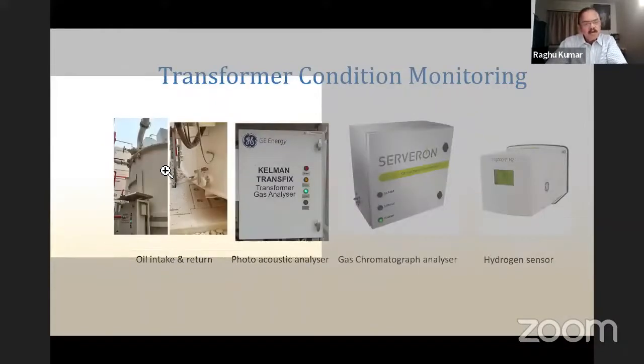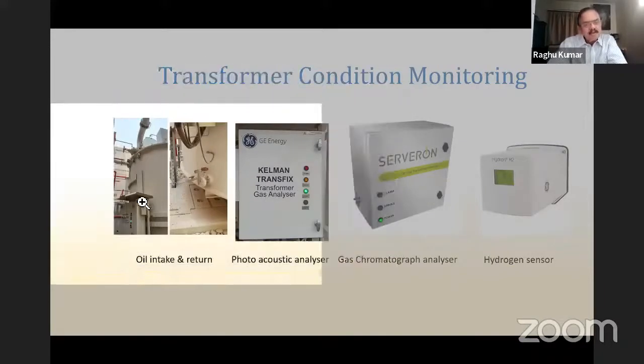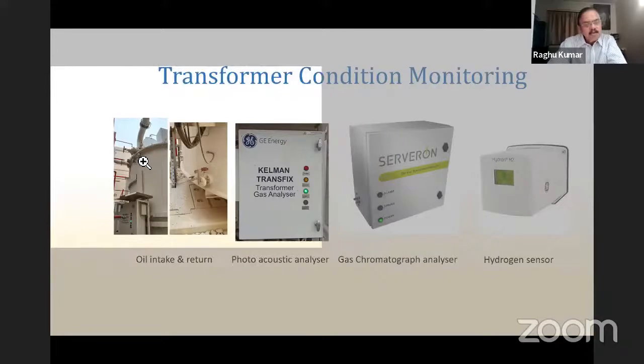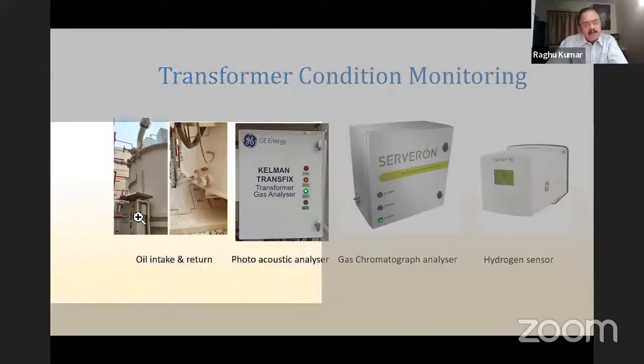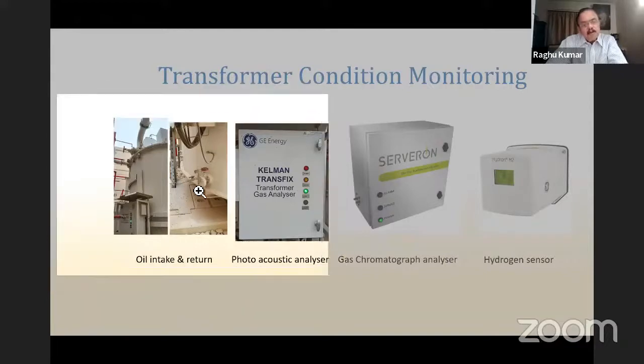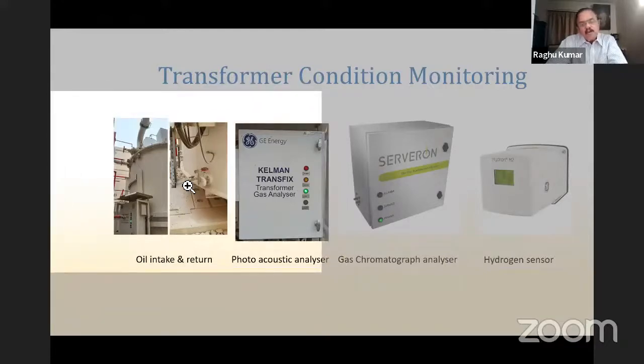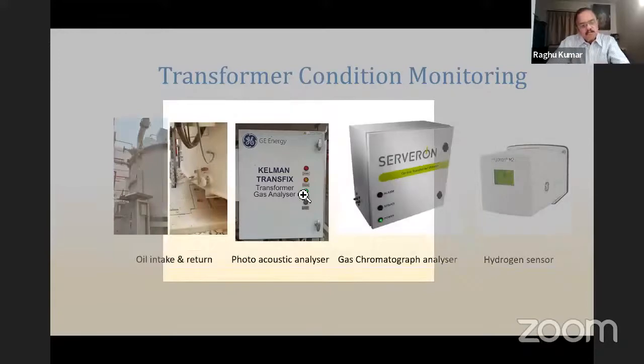And this is how the oil is taken up into the analyzer. See, from the top valve, oil is taken and then it comes into the analyzer. And once this process is over, it is pumped back to the bottom valve. So no oil is lost during the analysis process.